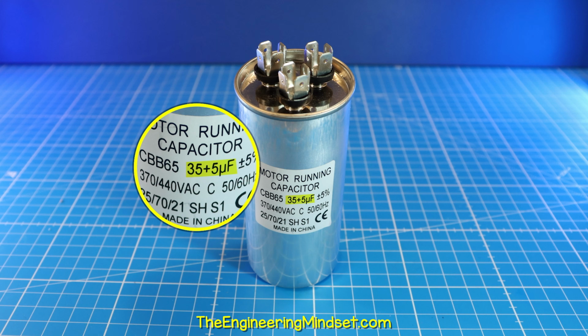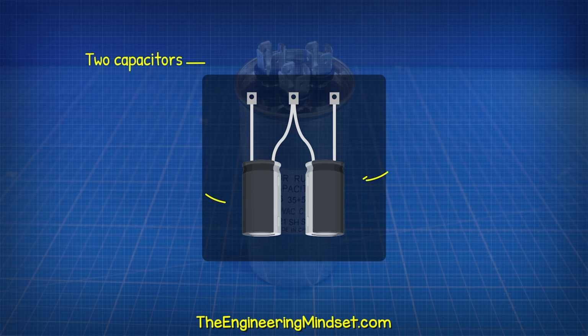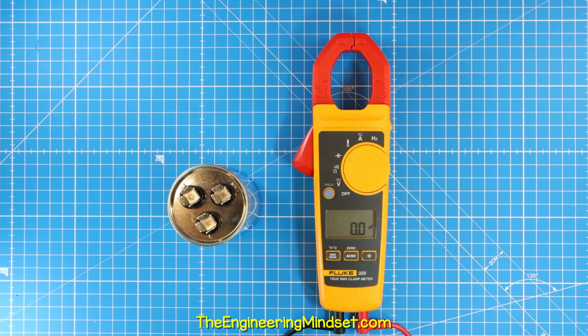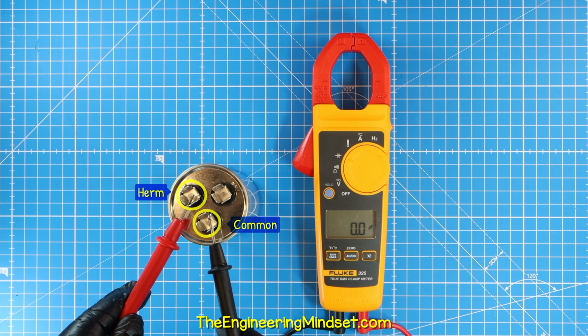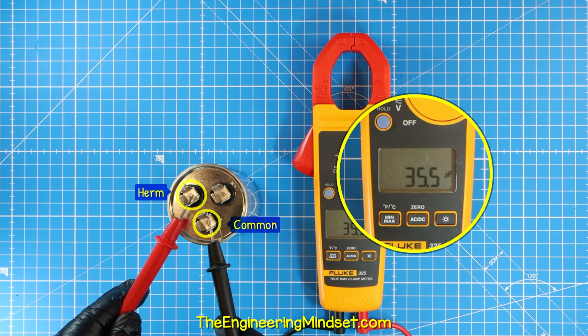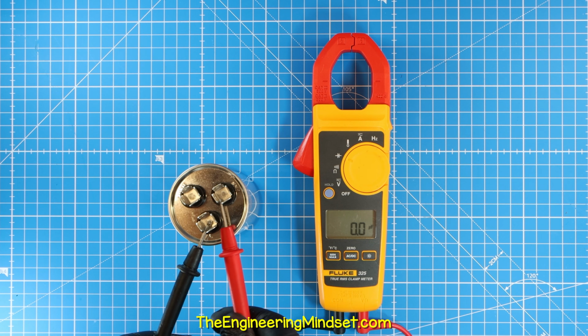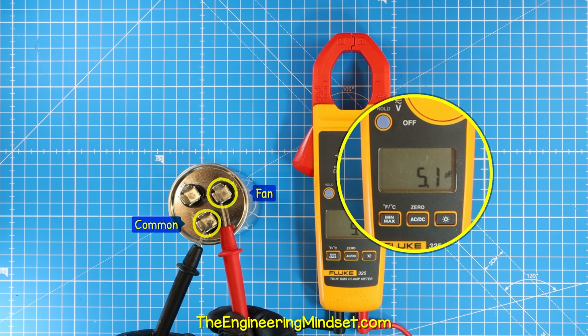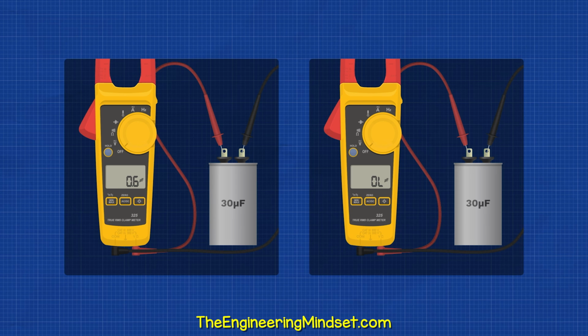This capacitor has 2 values because it's essentially 2 capacitors. If we measure across the Herm and common terminal, we should read 35 microfarads plus or minus 5%. If we measure between the fan and common, we should read 5 microfarads, again plus or minus 5%. If the meter shows a much lower value, or it just shows OL, it indicates that the capacitor is faulty or that the capacitor is beyond the range of your meter.